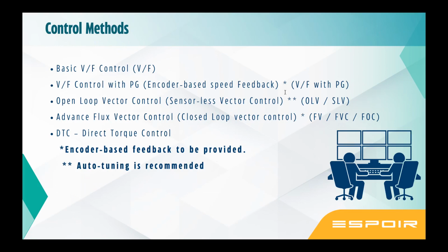You don't have to do it. The algorithm does this job. It will be maintained from 0.5 Hertz to 50 Hertz. Beyond 50 Hertz, in a VFD you can change the frequency above 50 Hertz also. You can increase the speed beyond the rated speed, but you have to be careful. The motors and the mechanical systems are designed to withstand a certain speed. If you go beyond that, it can damage the mechanical system. The bearings can break out. How much you can go depends on the application. Now, when you go beyond the rated speed, the torque comes down. You will achieve speed, but you will not achieve the torque required by the application. So you need to balance this act.